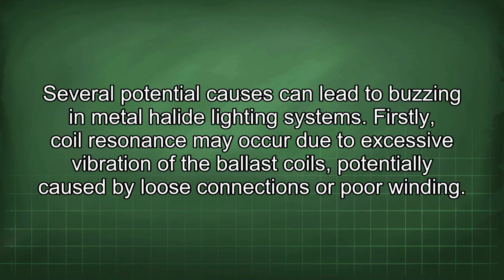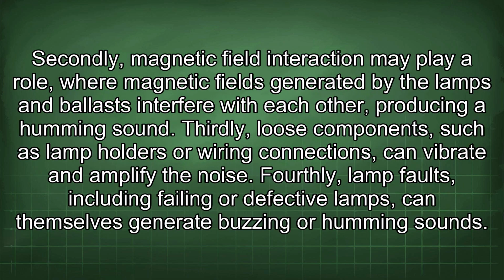Several potential causes can lead to buzzing in metal halide lighting systems. Firstly, coil resonance may occur due to excessive vibration of the ballast coils, potentially caused by loose connections or poor winding. Secondly, magnetic field interaction may play a role, where magnetic fields generated by the lamps and ballast interfere with each other, producing a humming sound.